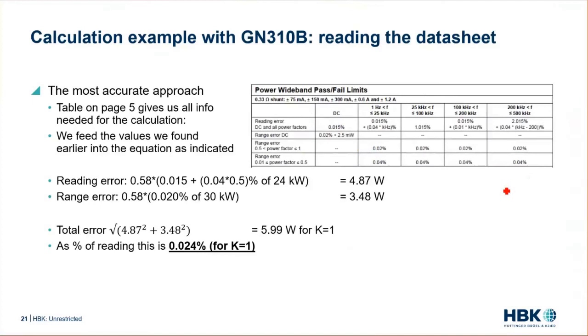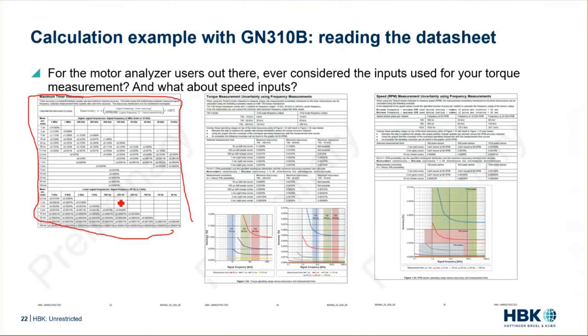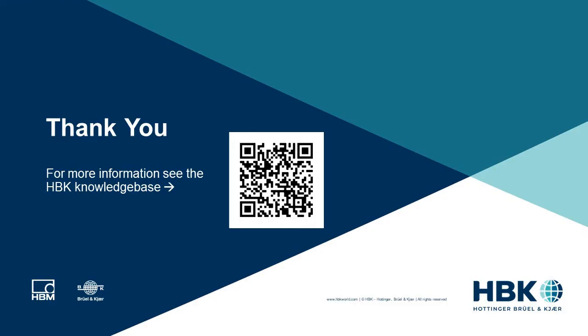Another thing to consider when reading data sheets: we just discussed the electrical inputs, but for anyone doing motor analysis, have you considered the measurement uncertainty of the inputs used for torque and speed measurements? Those are frequency inputs — counters — and they have a specific uncertainty that should be added to your measurement uncertainty calculation. Shown here are screenshots of the uncertainty contribution of the timer counters of the GN310B boards, which can be used to determine the additional uncertainty on torque or speed signals. For HBK or HBM torque transducers, those results are calculated immediately for your convenience.